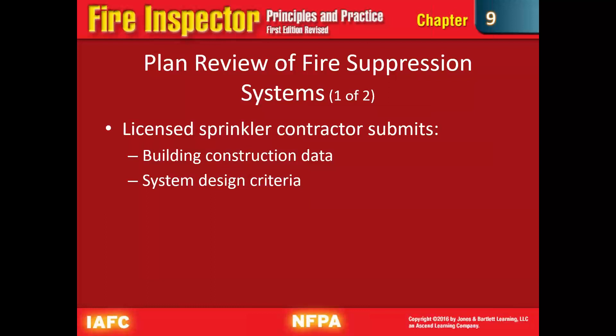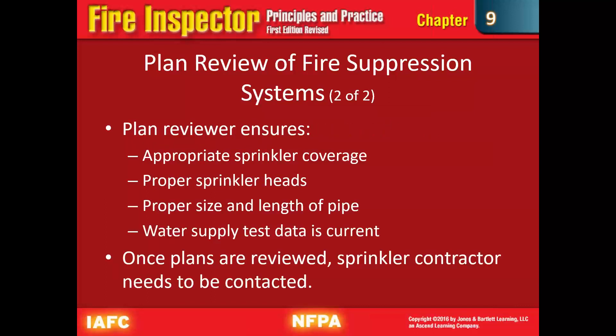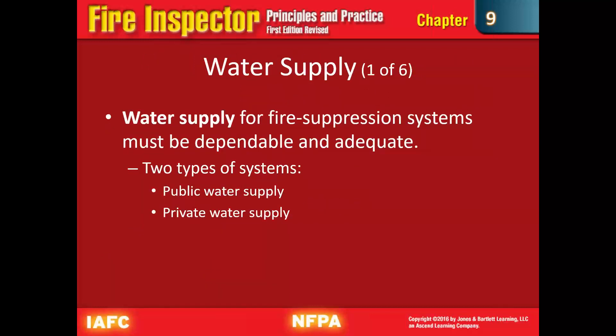A licensed sprinkler contractor submits construction and building data — including flow and pressure in the water system — and the system design criteria for the type and occupancy of the building. We ensure appropriate sprinkler coverage, appropriate sprinkler heads, correct pipe size and length, and adequate water supply, making sure the data they've received is current. Once reviewed, the contractor is contacted to let them know whether the plans are approved or denied.